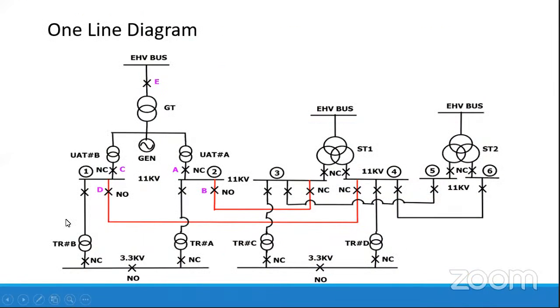So here, to protect the system, we need to see this single line diagram, how the existing network is connected and feeding the power to the network. Normally the coordination is done for the overcurrent protection. For voltage protection, the voltage protection comes as a separate protection feature. But the coordination is done for overcurrent, on the basis of current and time discrimination.